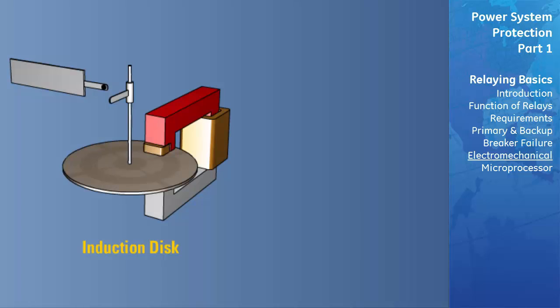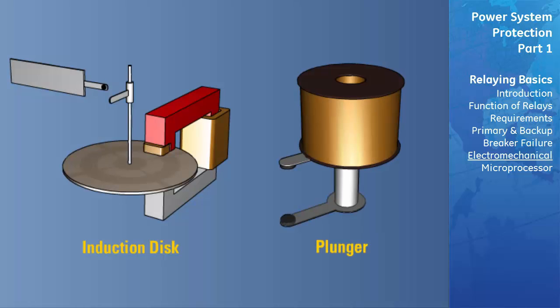In electromechanical relays, a moving part like a disc or a plunger is placed in a magnetic field produced by the input signals known as actuating signals or measured quantity. The disc or the plunger moves and touches a contact when the intensity of the magnetic field exceeds a preset limit.